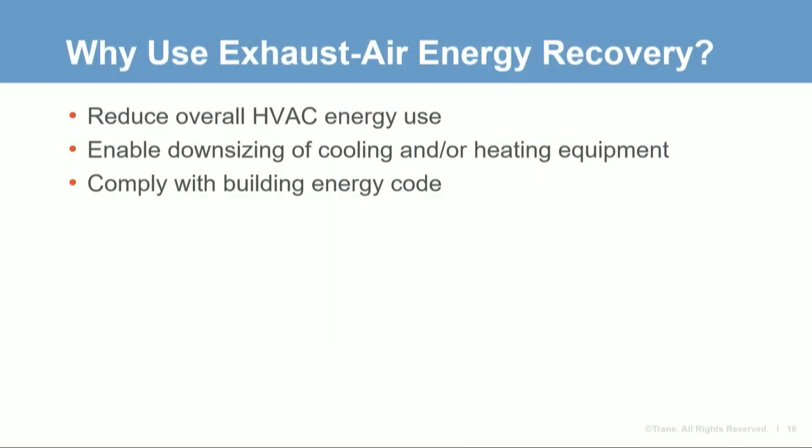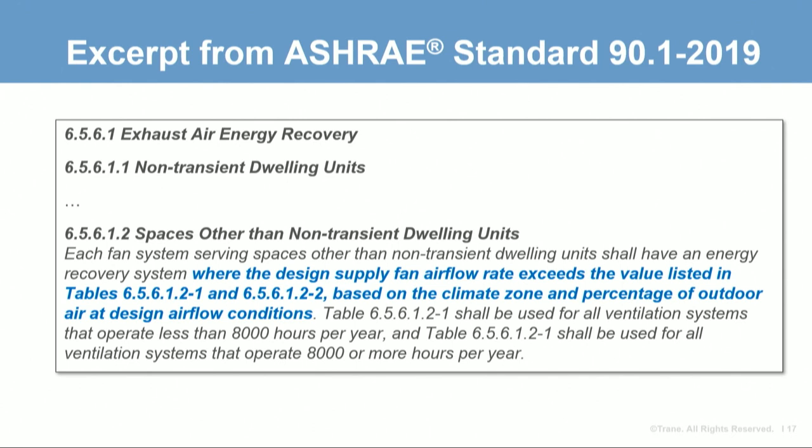Sometimes exhaust air energy recovery is used simply because it's required by the local energy code or building rating system. ASHRAE Standard 90.1, used as the basis for many state and local codes, includes prescriptive requirements for exhaust air energy recovery. The requirements in your local code may differ depending on the version being enforced in your jurisdiction. Here's an excerpt from the 2019 version of that standard. Note that there is a different set of requirements specifically for systems serving non-transient dwelling spaces such as apartments.